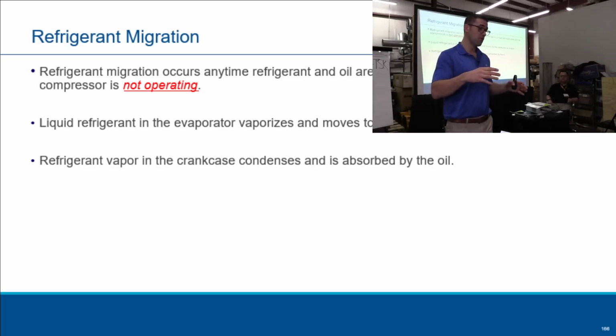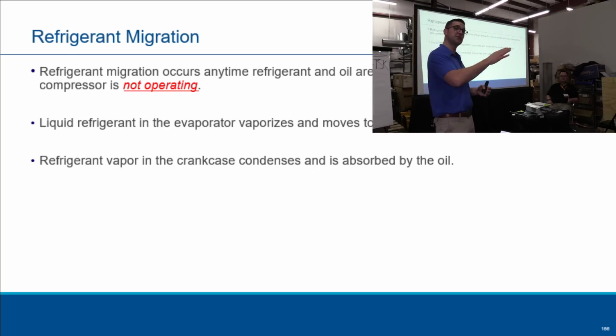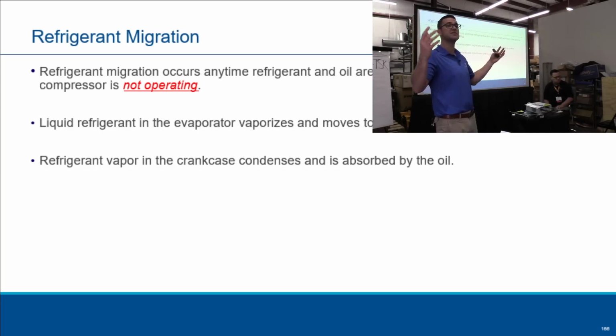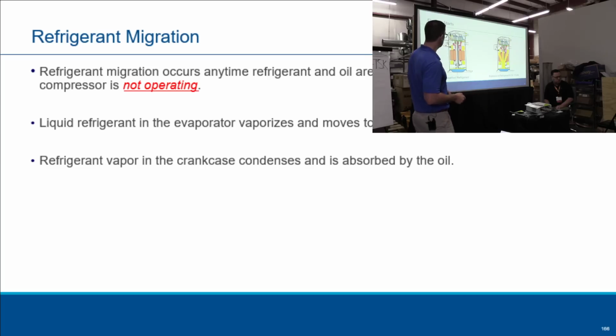So that refrigerant, as a gas, travels through the system, migrates to the coldest part, which could be that compressor. That crankcase is not working that day. It stratifies inside the oil, and then you start up, and it explodes that refrigerant all over the insides of that scroll. Like this. So it migrates back, stratifies, and then you get an explosion. And it's loud. The compressor's loud.